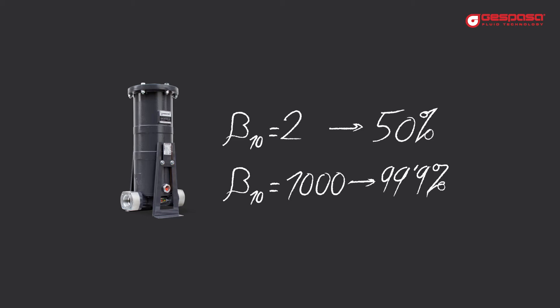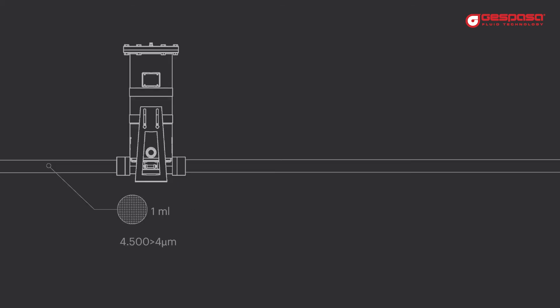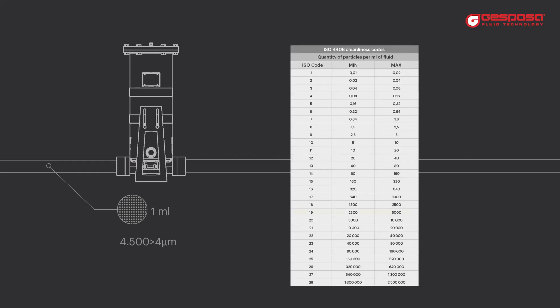Let's imagine that we have diesel with 4500 particles larger than 4 microns in a milliliter. This would be the equivalent of an ISO 19 code. We want to get to code 18, that would be having less than 2500 particles in a milliliter of diesel.